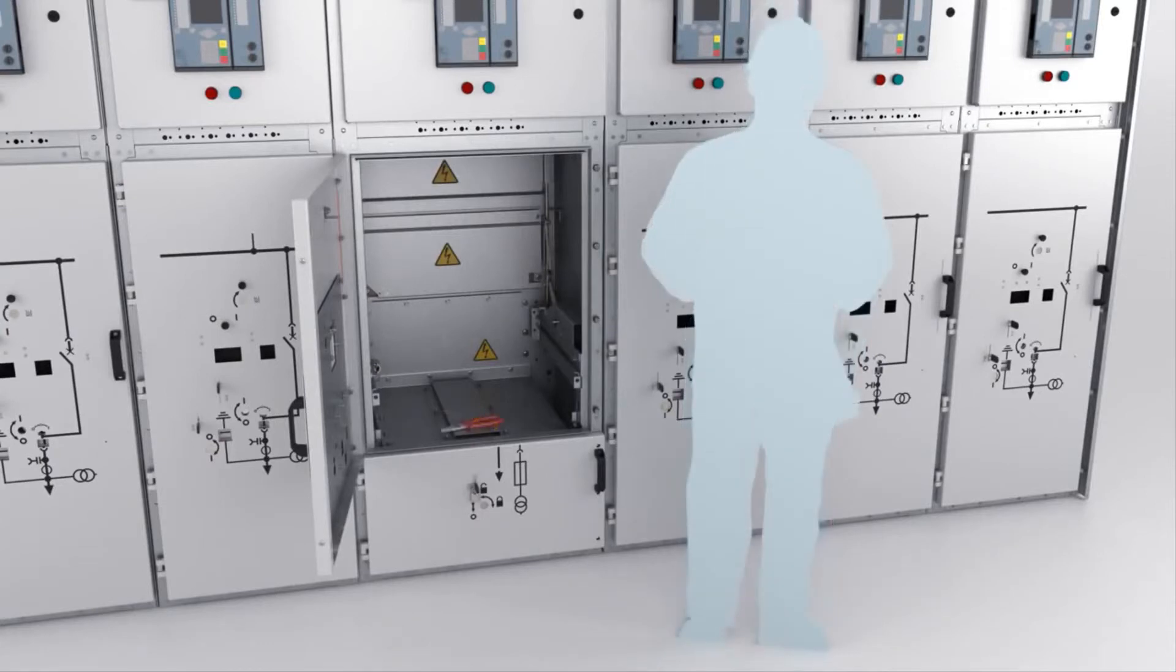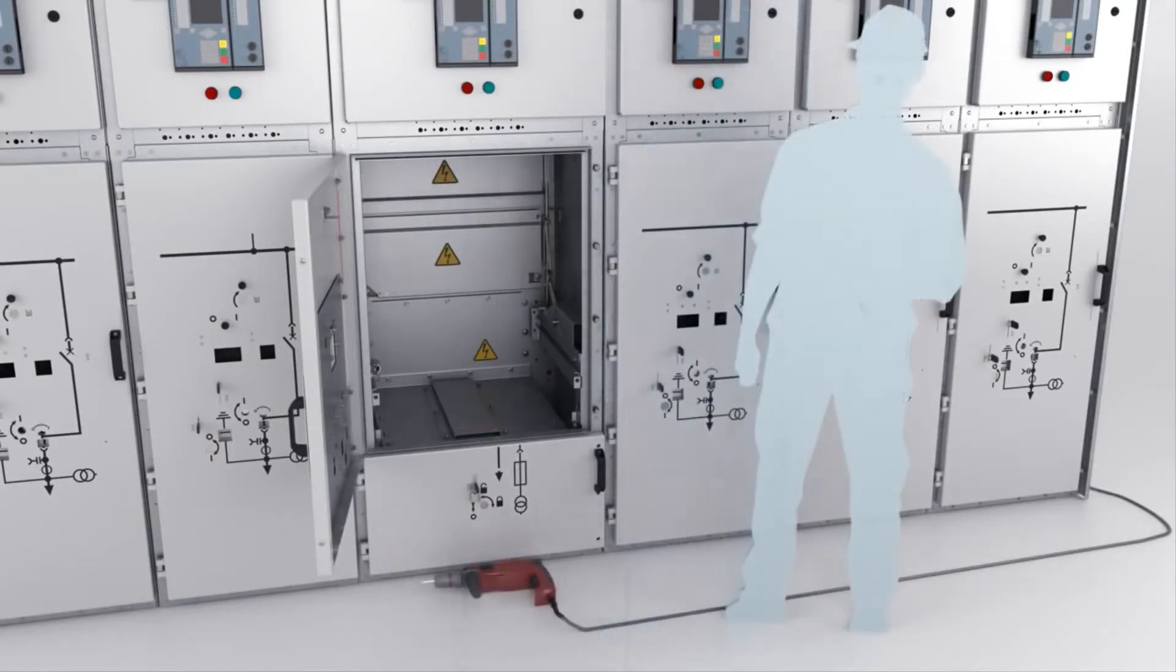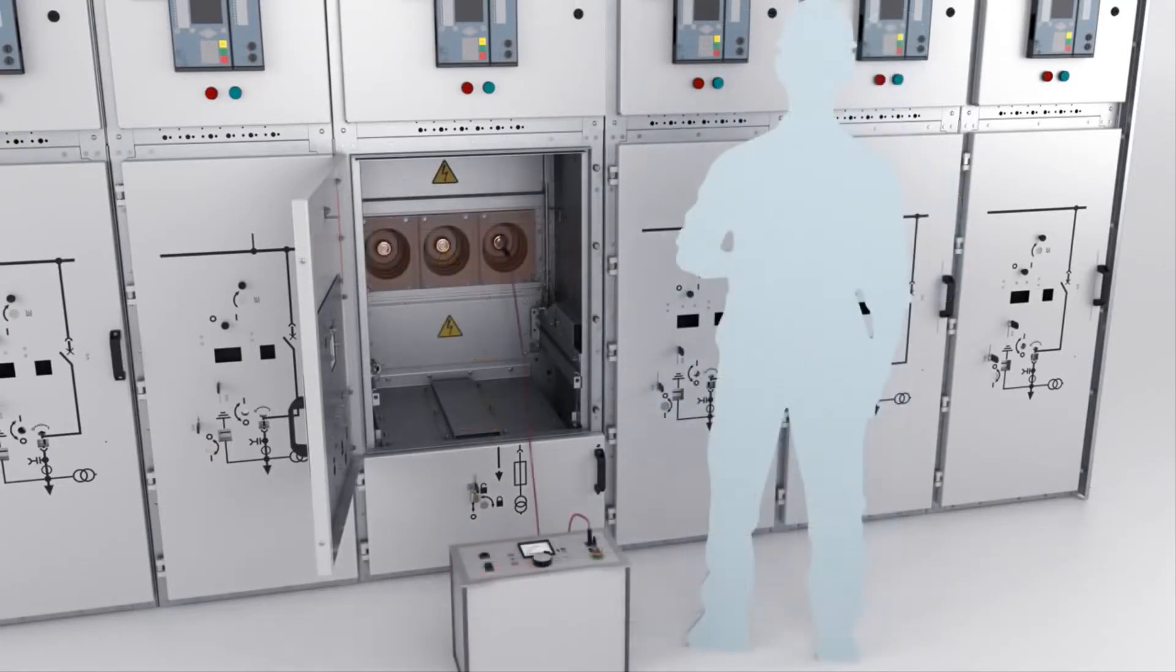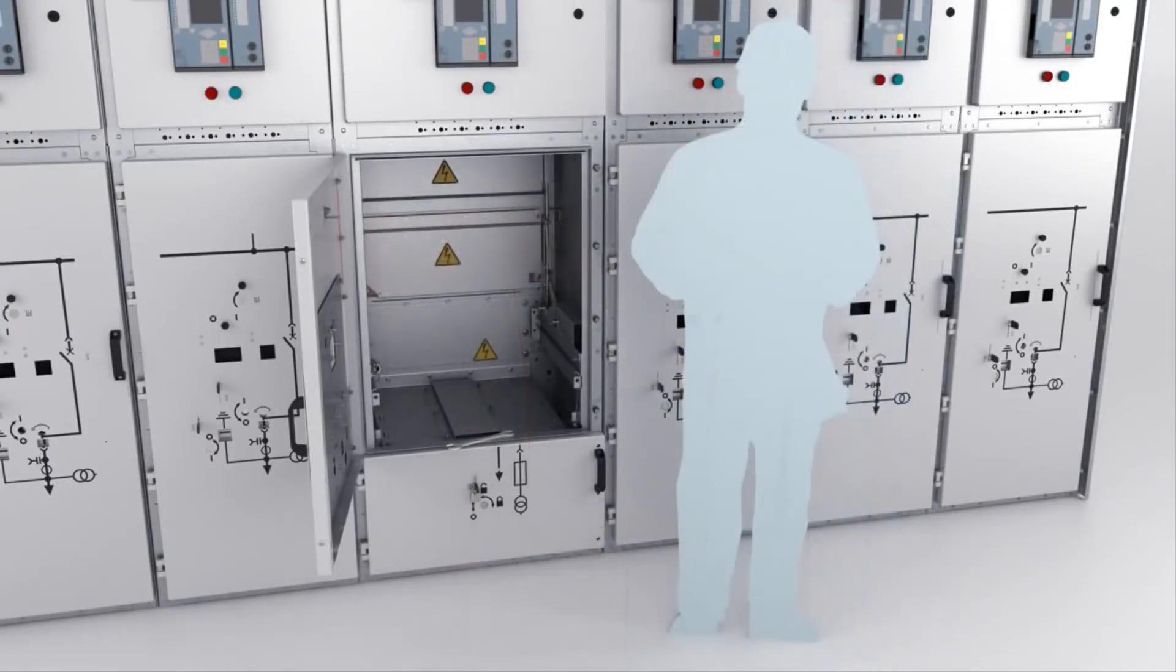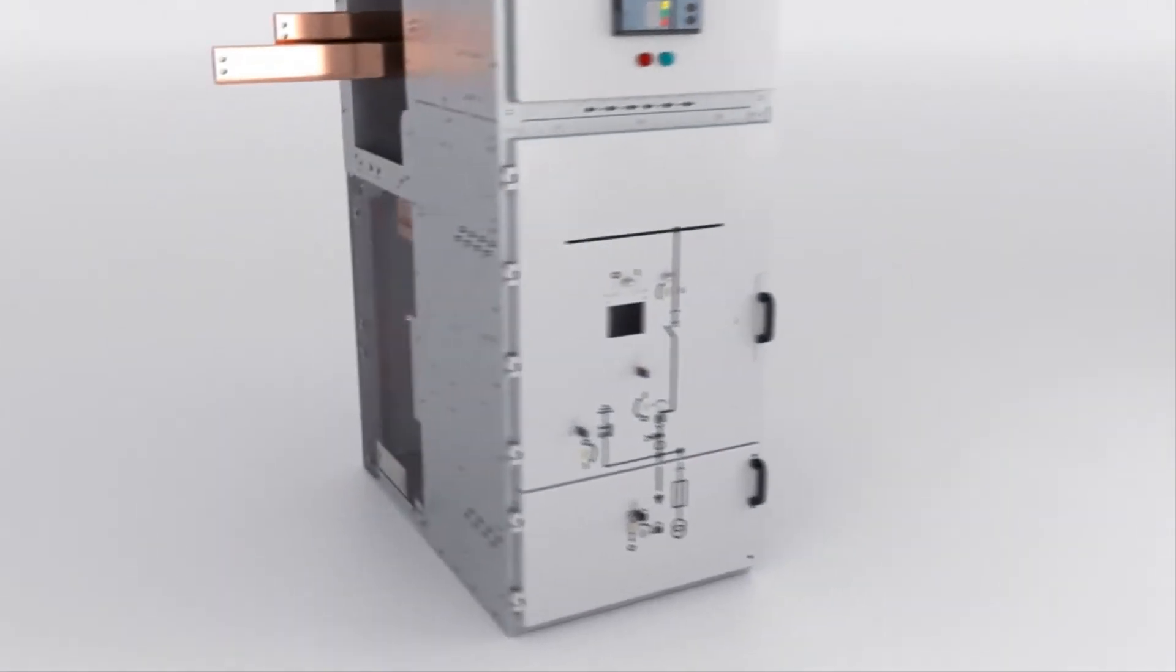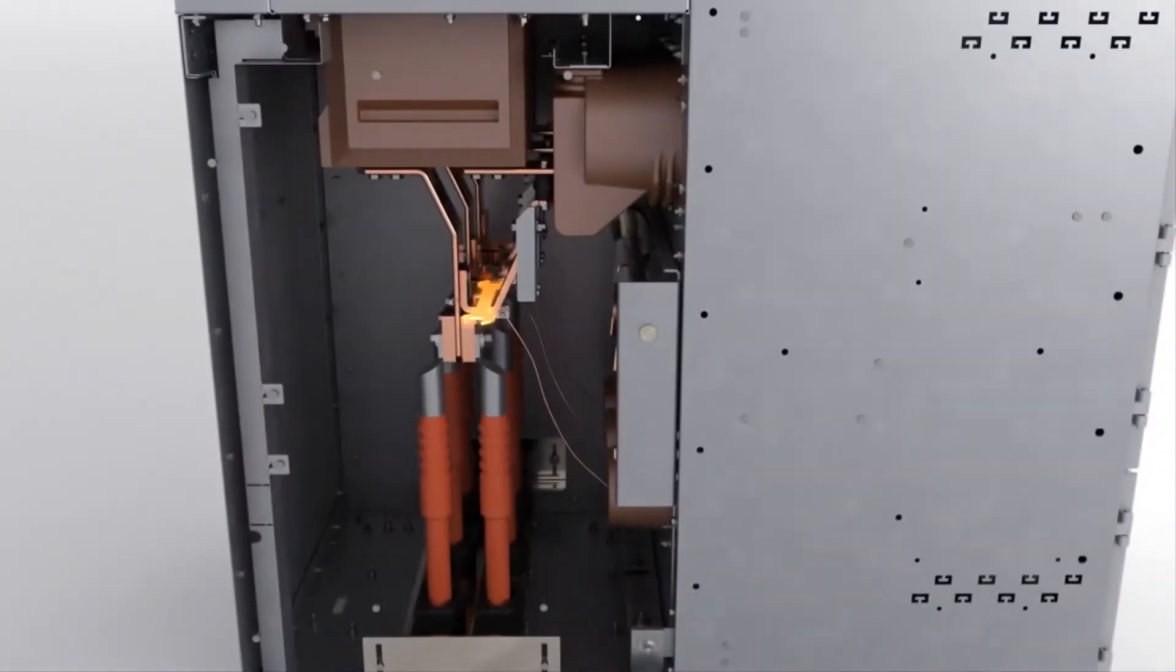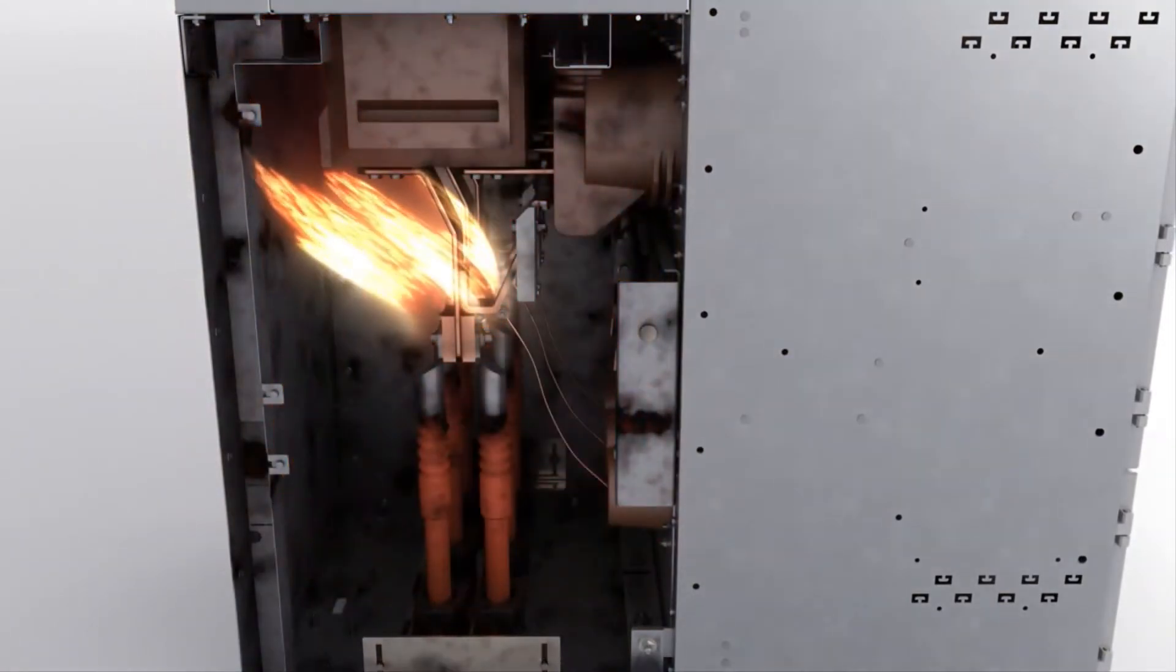Malfunctions can be caused by internal arcs, for example by dielectric faults in transformers, at cable sealing ends, or by tools being forgotten after repairs, thus leading to downtime.